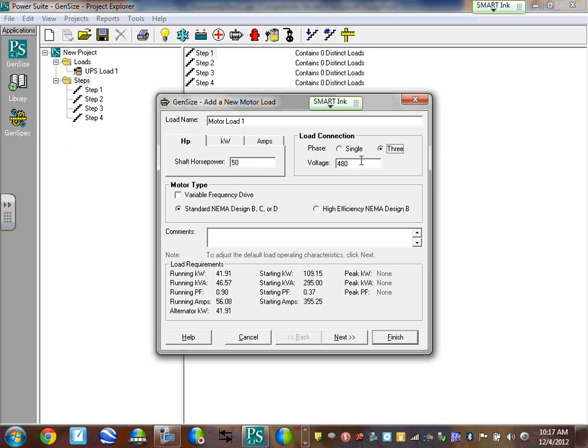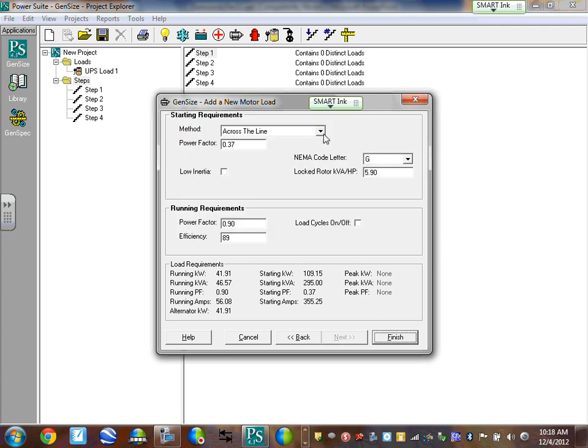On motors, it's very good to look at the type of motor and motor starting that you have. Help me out here, next. Across the Line. Okay, here we go. This particular box, you're going to see on a lot of the larger motors, chillers maybe in large buildings might have a VFD type of drive or a solid state starter. Those are very common ways to get a motor running with the least amount of power. So they're actually pretty good with generator sets.